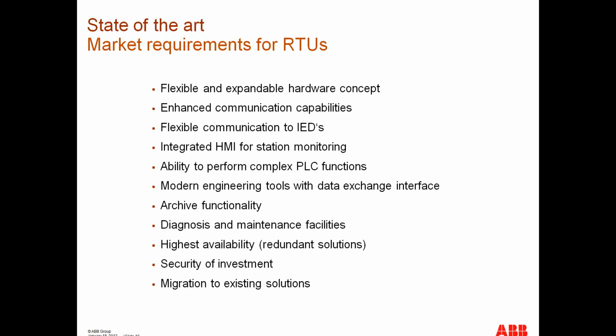Then a market requirement is the flexible communication to IEDs, meaning what I said before, not only to the control center but also to the IEDs. Then the integrated human-machine interface for station monitoring, so that you can really see your grid and see which position, for example, a circuit breaker has right now at the moment. As well as the complex PLC functions. And then another market requirement was the modern engineering tools with data exchange interface, meaning that to engineer and program the RTU as easy as possible.